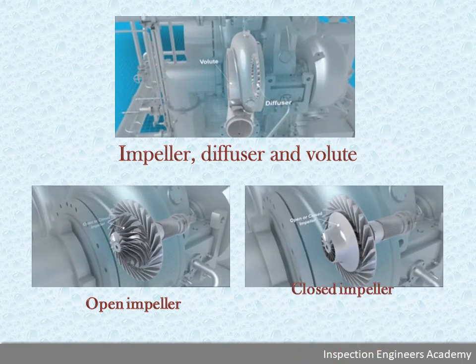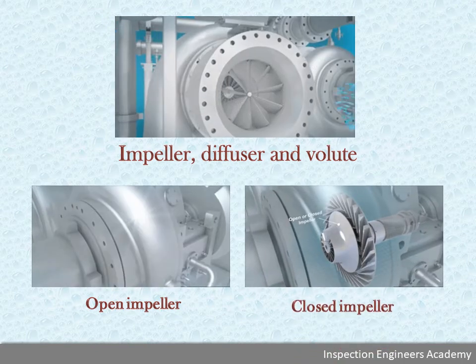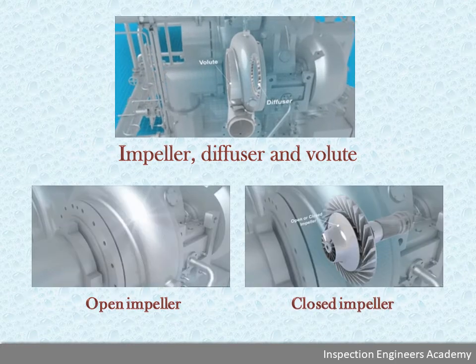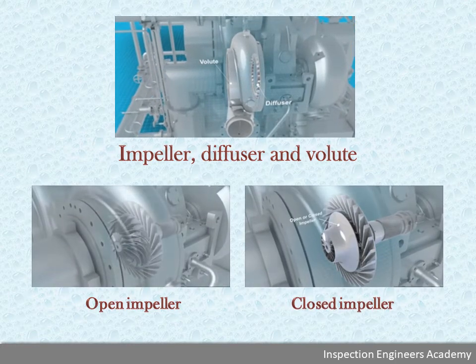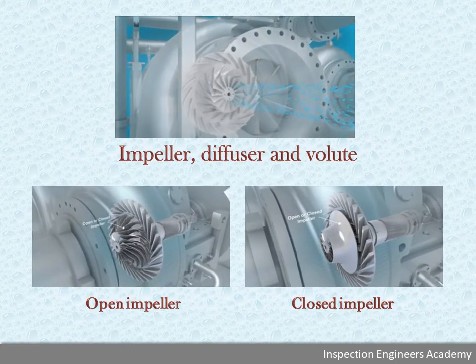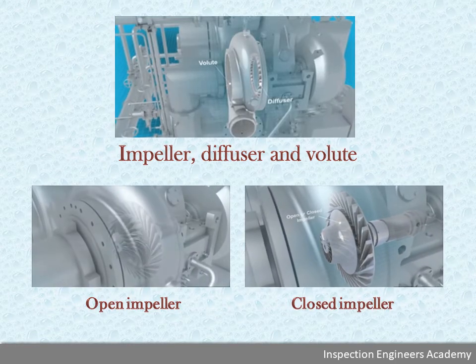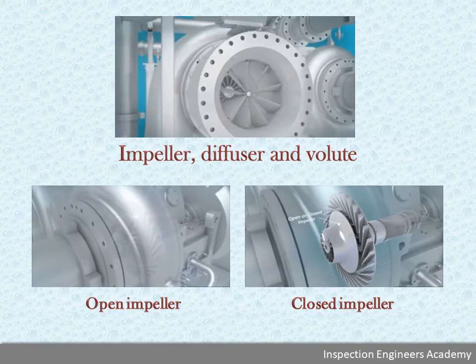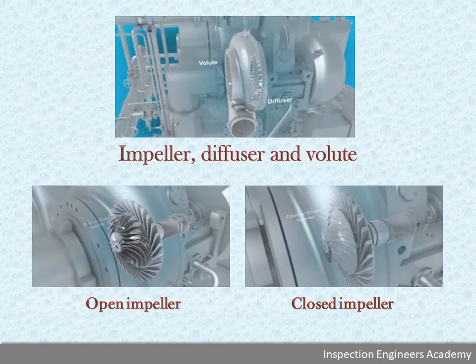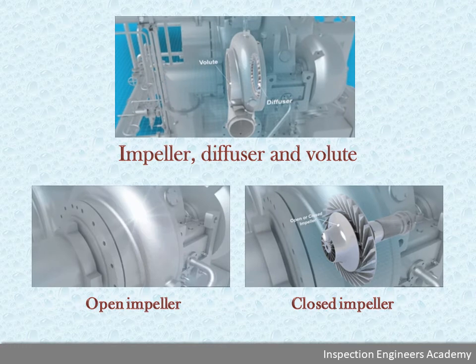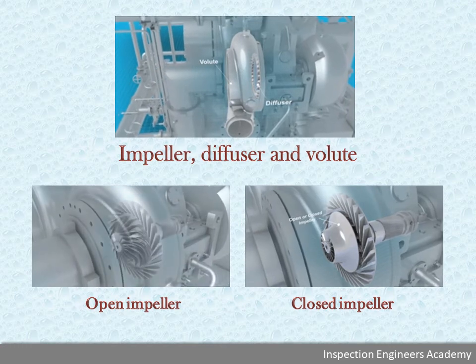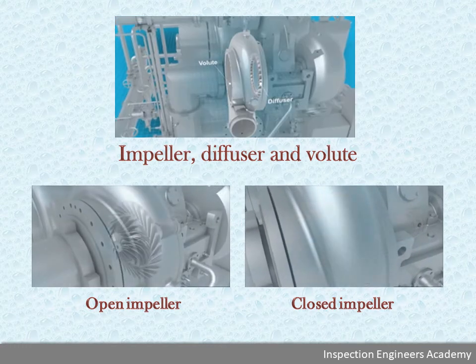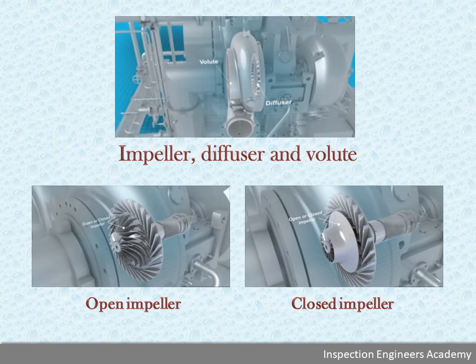In the enclosed design, the vanes are sandwiched between two discs. The open design has to deal with gas leakage between the moving vanes and the non-moving diaphragm, whereas the enclosed design does not have this problem. However, the enclosed design is more difficult and costly to manufacture.